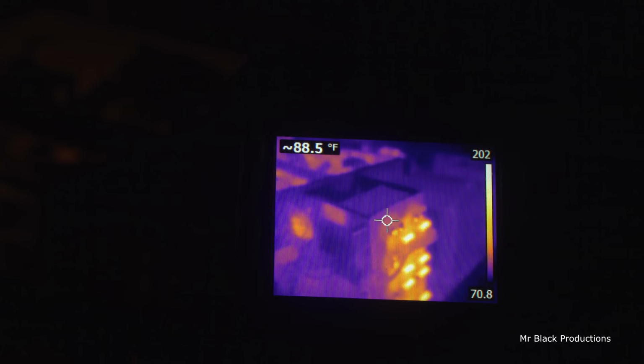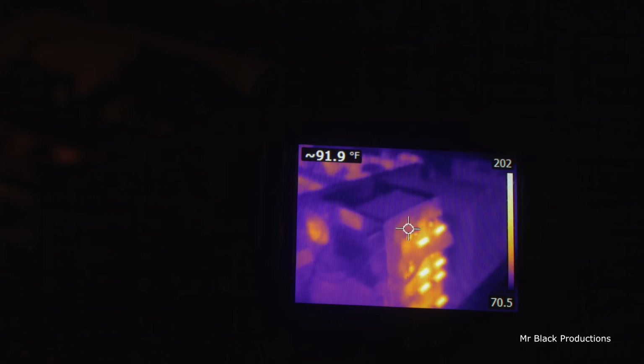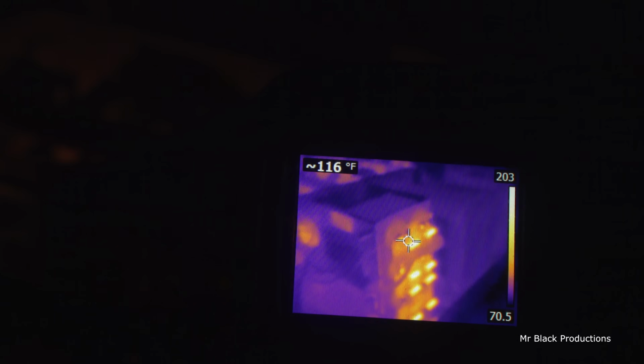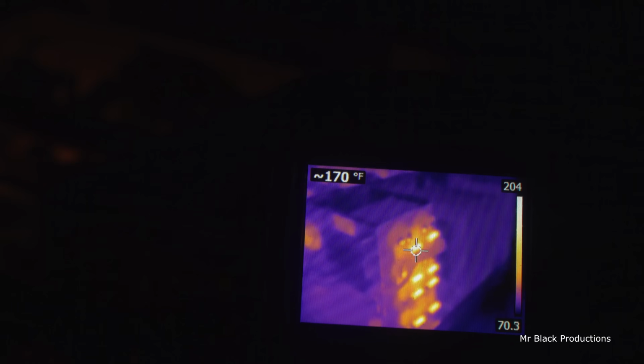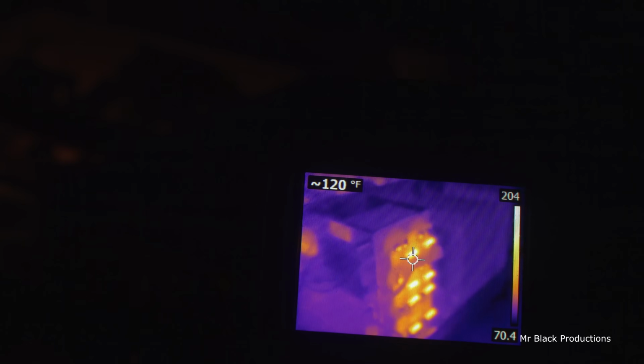The capacitors on the back side behind the bleeders are at 80 something degrees. The bleeders themselves are at about 200, which is more than safe. It's really important that I establish this baseline, keep this running for a little while, and we just sit back and watch it.